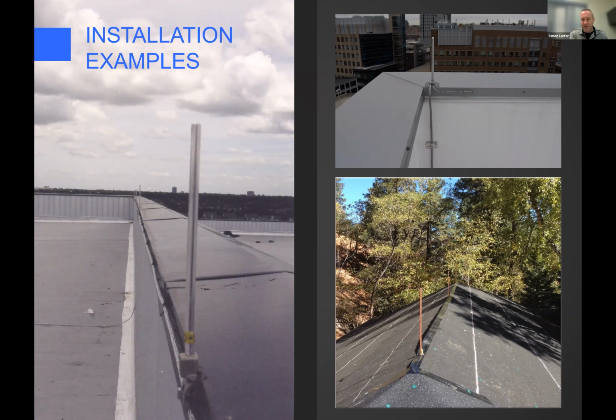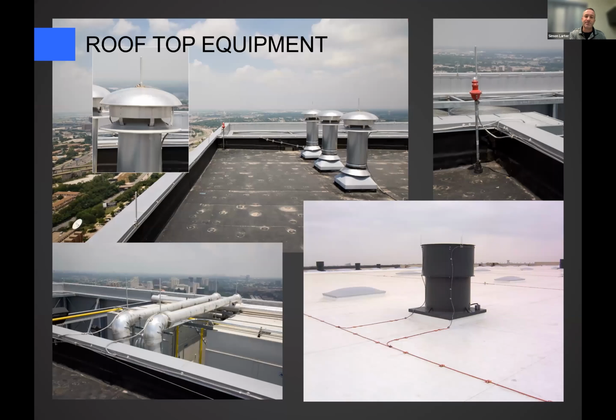The aluminum is thicker and more substantive than the copper. The minimum size for a copper rod diameter is 3/8 of an inch, 10 millimeters. But for an aluminum rod, the minimum diameter is going to be 1/2 an inch, 12.7 millimeters. So if you see the aluminum stuff, it's a bit chunkier than the copper would be, but that's because it's slightly less conductive, so we give it a bit more material.